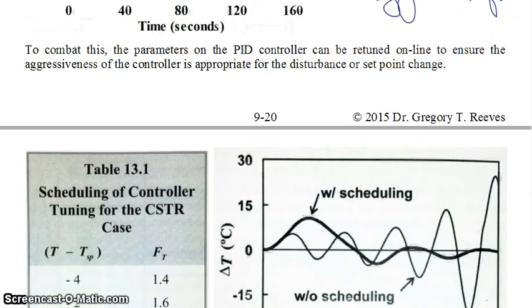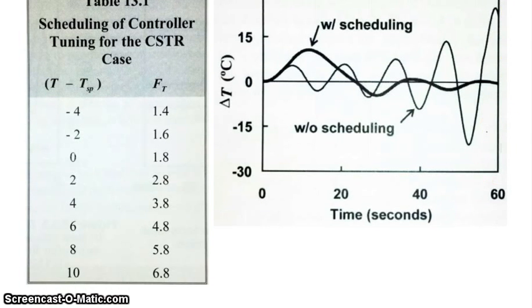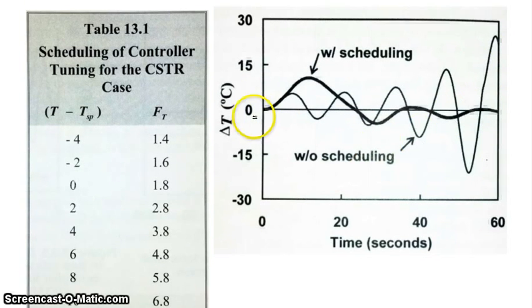So for example, and this is called controller scheduling, right? Because what you have, I mean it's an old school term, but what you basically have is you have a schedule or a table which says, okay, so if the difference between my product temperature and my set point becomes this value, then I want to make a parameter called FT take on this value. If my difference in objective and set point is this value, then I want the value of some tuning parameter FT to be this value, etc. And so this is called scheduling.